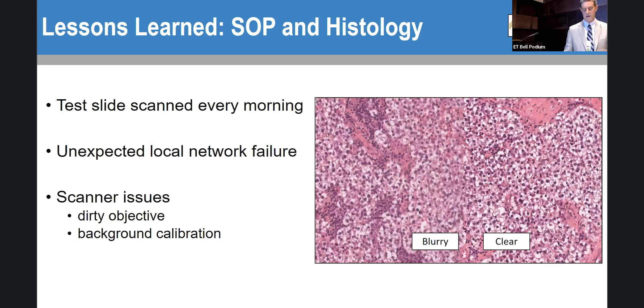Other things, scanner issues, background calibration issues, particularly if the light source was fading. That was a lesson that we learned over time. If the light bulb was ending its lifespan, we would notice calibration issues. And a dirty objective. So if you did get some mounting media on the slide or on the objective and it dried, you would get this film, and then you would get this striping that you're seeing here. Where you see blurry on the right-hand end of one stripe, and it's perfectly focused on the left-hand end, and that would just repeat itself all the way across the slide. So then the objective could be cleaned again before frozen sections arrive.